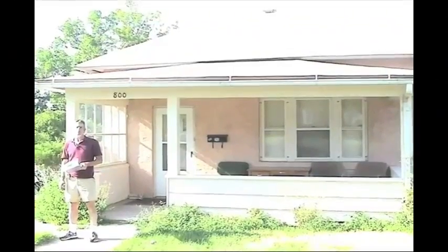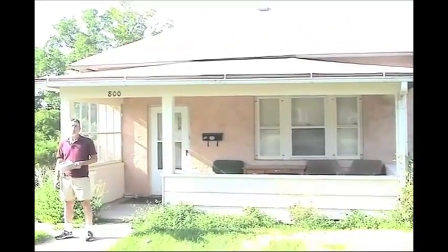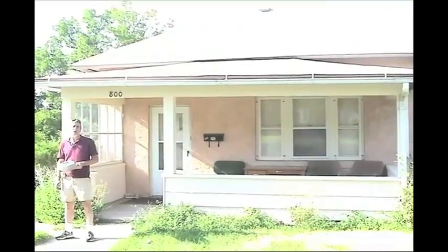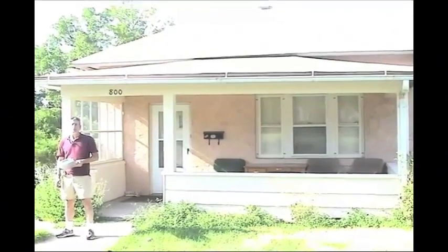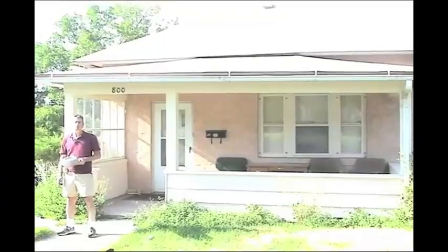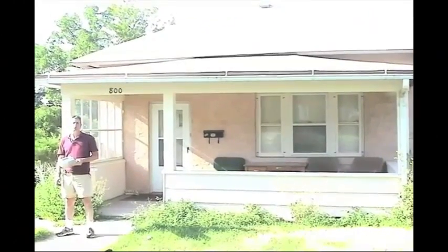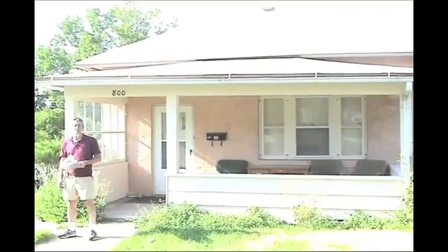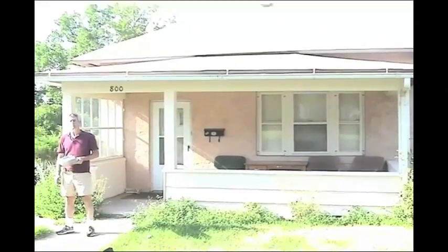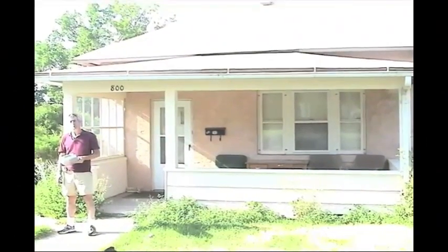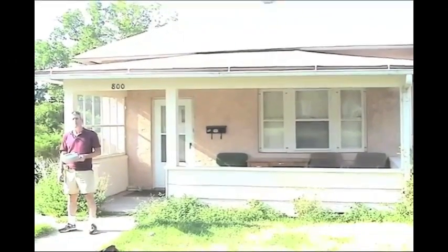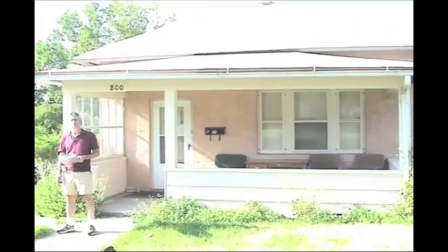While you're measuring the exterior dimensions of the house, you also need to be looking for different types of walls. You may have a different R-value in different parts. There may be an original house that's got additions added to it. You'll have an opportunity once you're inside the house to probe behind cover plates or behind electrical panels and get some idea what the insulation material and thickness may be in those areas. But oftentimes at the outdoors, you'll get the first hints of those different wall types. Be sure to note those on your forms. And if you do see they're different, you may have different wall sections. Wall section number 1, wall section number 2, and wall section number 3, for instance.